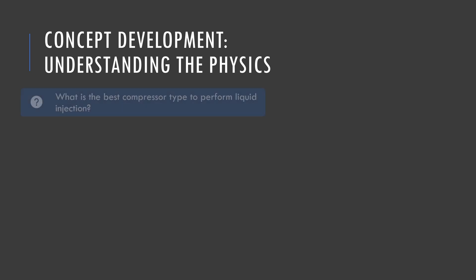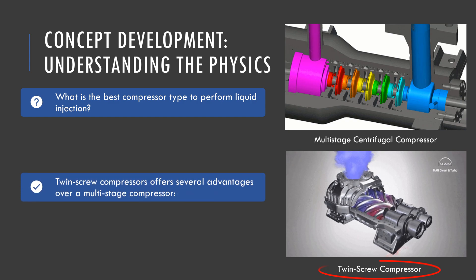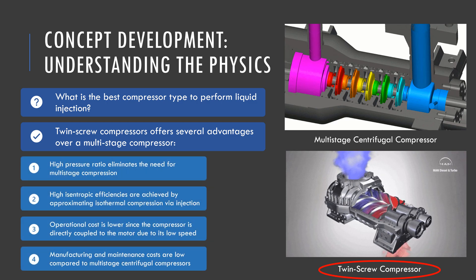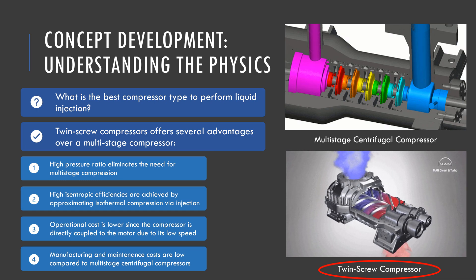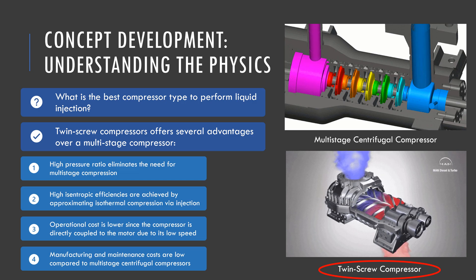The best compressor type to perform liquid injection for a wet compression process is the twin-screw compressor. Compared to a multi-stage centrifugal compressor, it offers a higher compression ratio eliminating the need for multi-stage compression, higher isentropic efficiency due to injection, lower operational cost because the compressor is directly coupled to the motor due to its low speed, and lower manufacturing and maintenance costs. As a result, a single-stage water-injected twin-screw compressor is chosen in this study to improve the performance of the system.